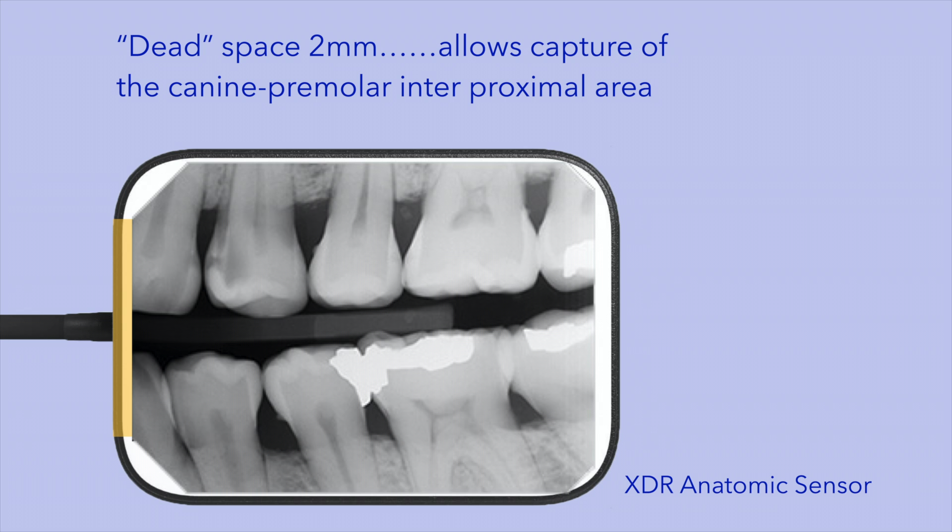With the XDR sensor, the dead space at the corded end of the sensor is approximately 2 mm. This allows us to better capture the area of the canine premolar interproximal region, which is a critical region that we capture on bite-wing radiographs.